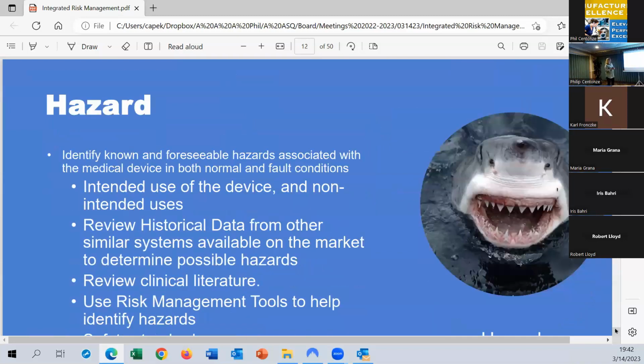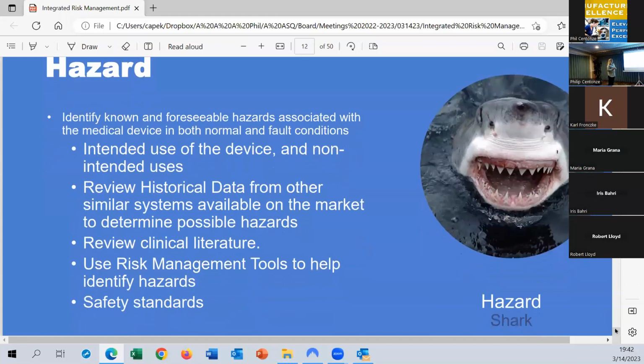All right, so what's a hazard? We want to identify known and foreseeable hazards associated with the medical device in both normal and fault conditions. So a hazard is something that can result in a hazardous situation that will result in harm. In our example here, a shark is a hazard, right? It's only a hazardous situation if you're swimming in the water with a shark, but a shark is a hazard.